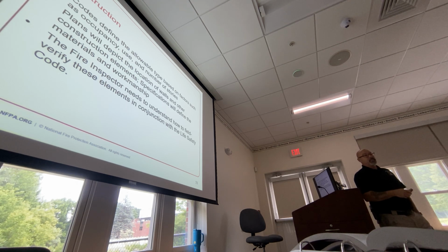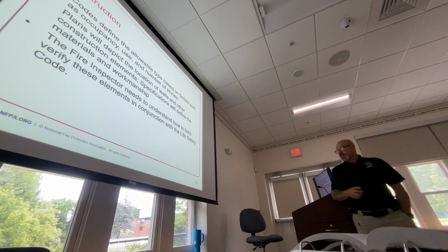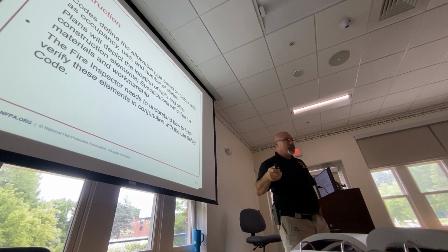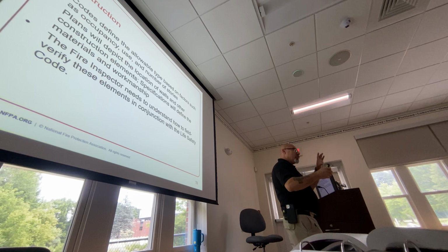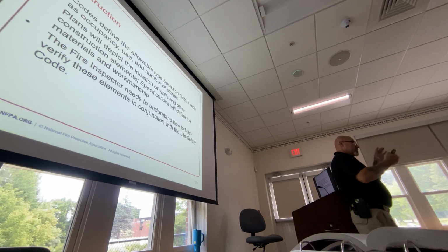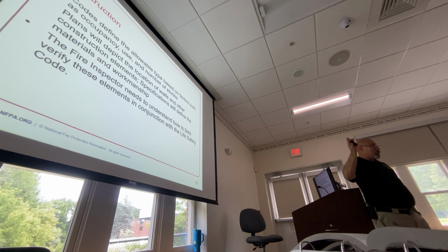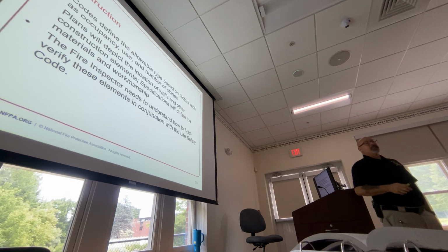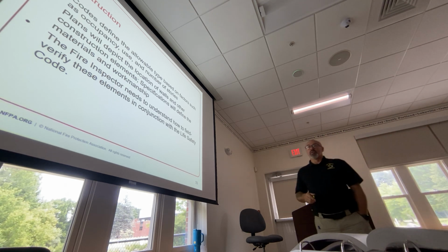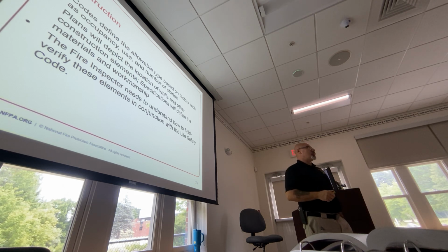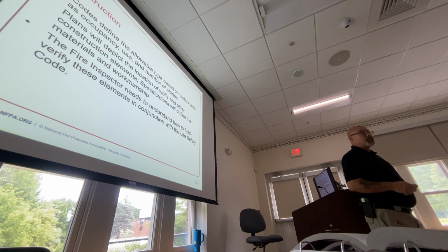It may be wood framed, hard to tell. Quite honestly, we can take an outlet cover off and look inside. The outlet is attached to a stud, right? You can look pretty quickly. Is it wood framed or is it steel studs? That'll give you a pretty good clue of what you're dealing with. And then you can go down through the checklist of NFPA 220 and see what you have for items.